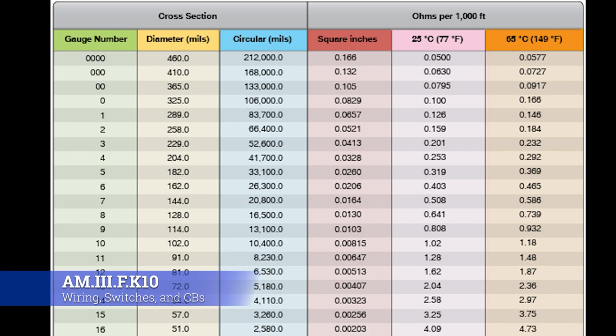Mostly on your avionics stuff, you're going to get anywhere up to about a 14 gauge wire—typically you'll see like 16s to 24, somewhere in that range. You get like 16, 22, 14, and you'll see some 18s every once in a while. For heavier gauge wires, like your battery cables, starter cables, and stuff that has to carry a lot of current, you're going to get larger gauges, but these are few and far between—only a handful of them, and they may be up to anywhere between 4 to 9 or so, depending on the load it has to carry in the aircraft it's on. You can also see on there the ohms per 1,000 feet.